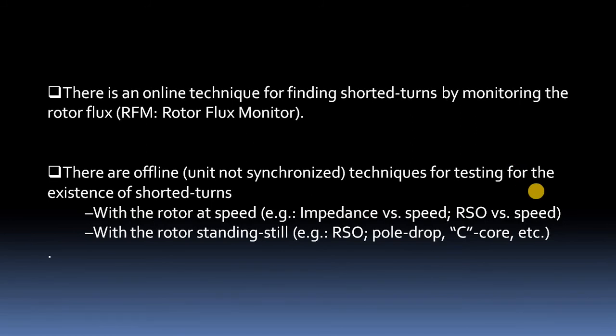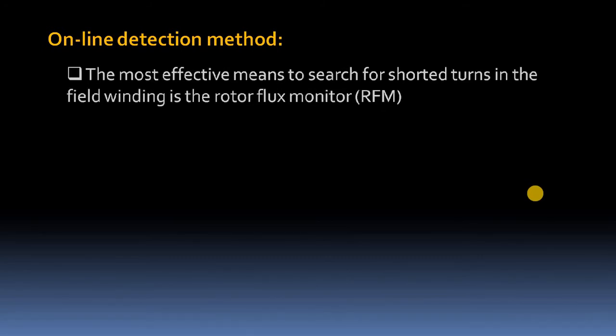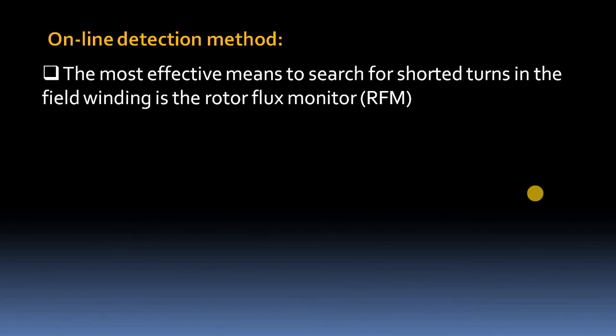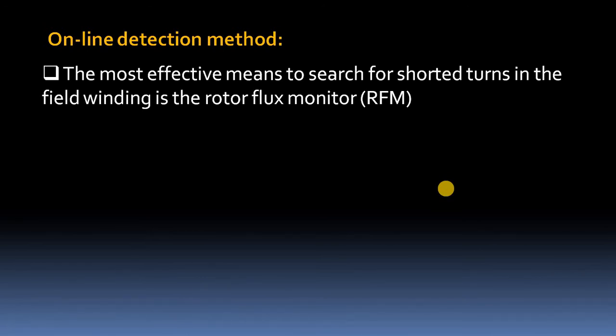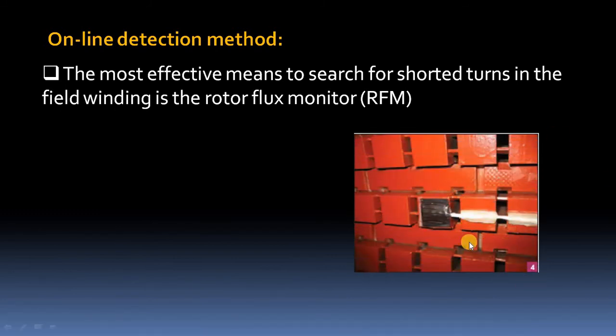Here we concentrate on the simple pole drop test as an offline technique, but we will also see the online technique briefly. In the online detection method, the Rotor Flux Monitoring technique is used. As the name indicates, we monitor the air gap flux or rotor flux by placing a sensor at the tooth of the stator winding. The sensor placed on the face of a stator tooth monitors the rotor flux, and from the resulting rotor flux plot we can identify which pole has shorted turns.